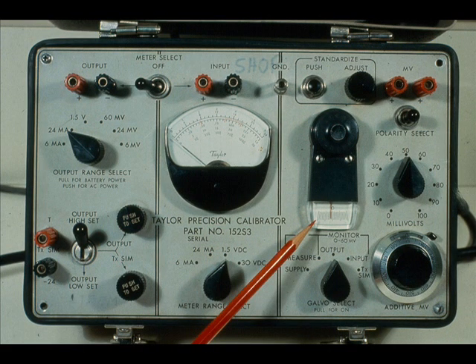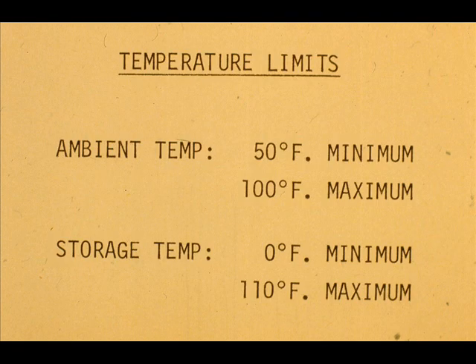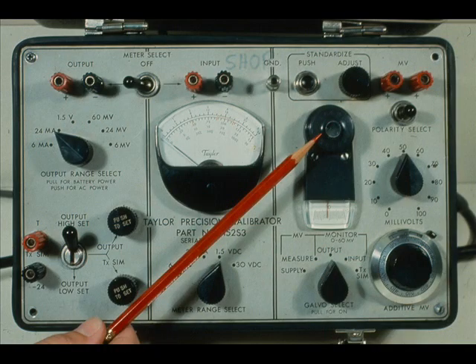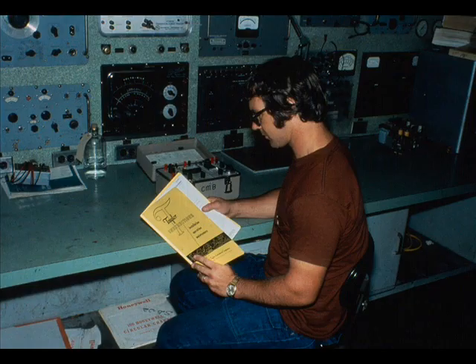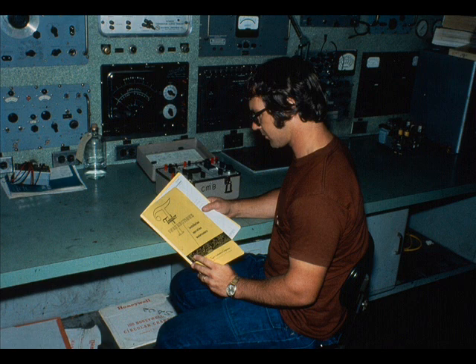It also has a transmitter simulator section. When more accuracy is desired, the galvanometer is used as a null meter for either the input or output signals. The ambient operating temperature limits are determined by the wet type standard cell in the potentiometer section. The galvanometer is delicate and should be clamped when not in use. Read the instructions thoroughly before attempting to use the calibrator.